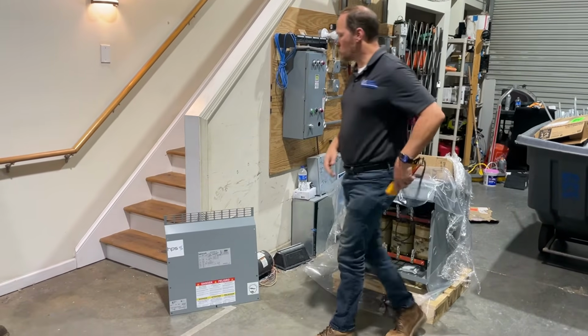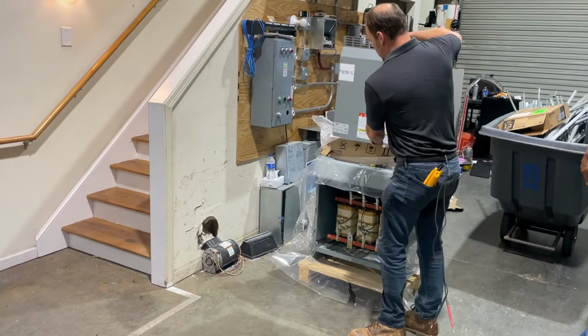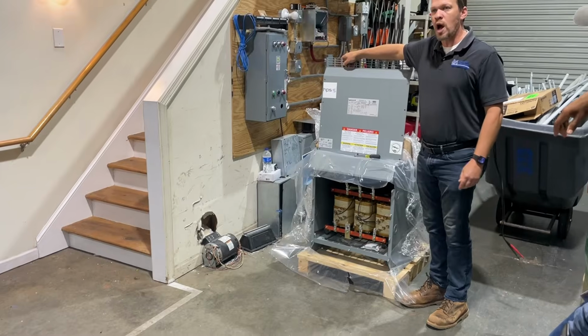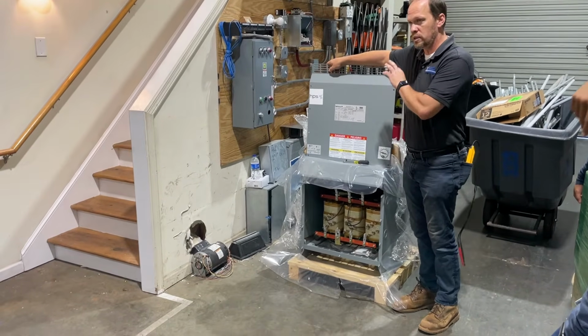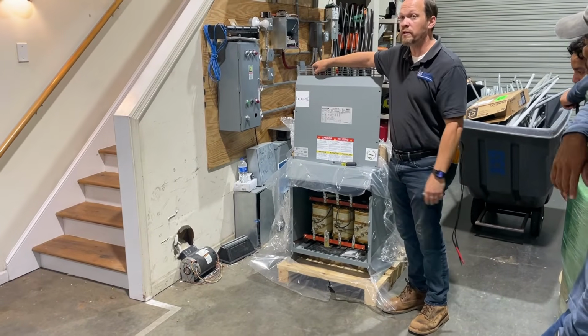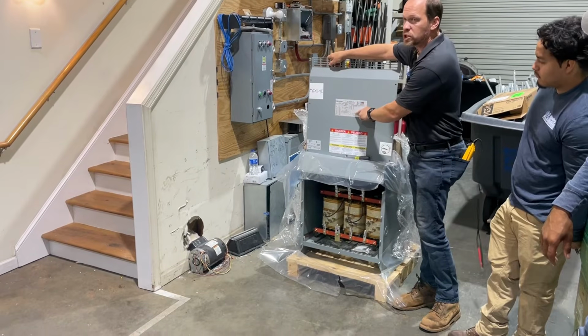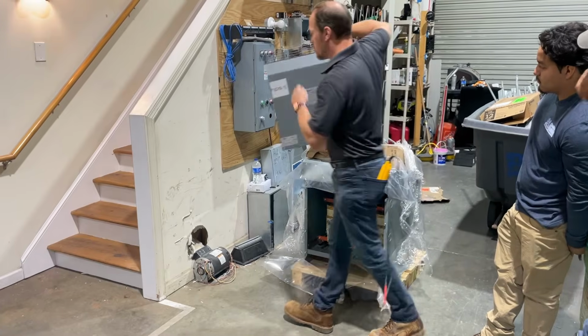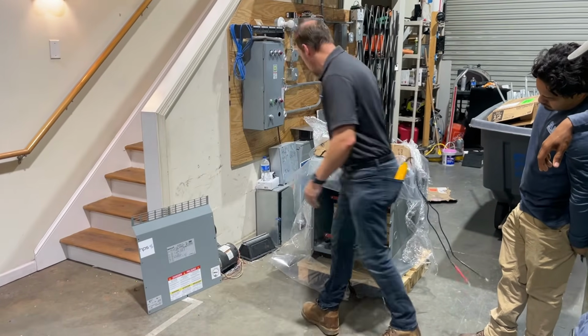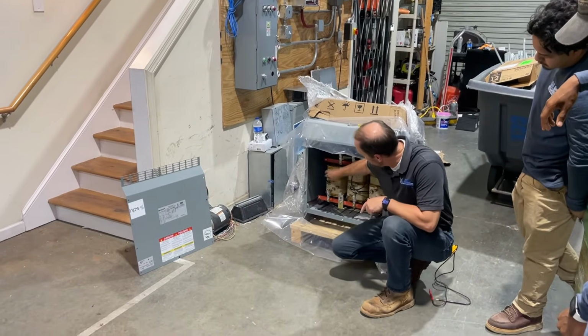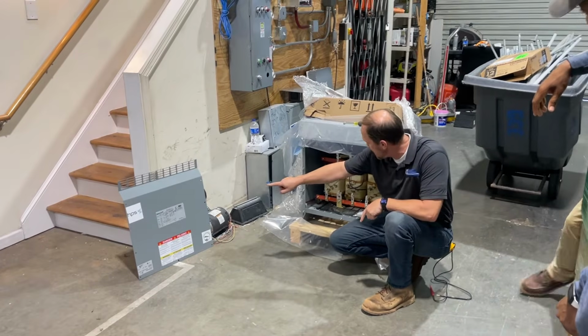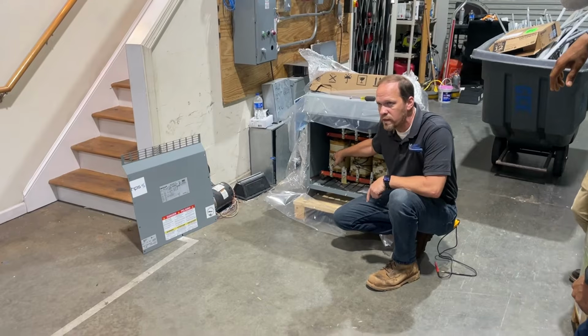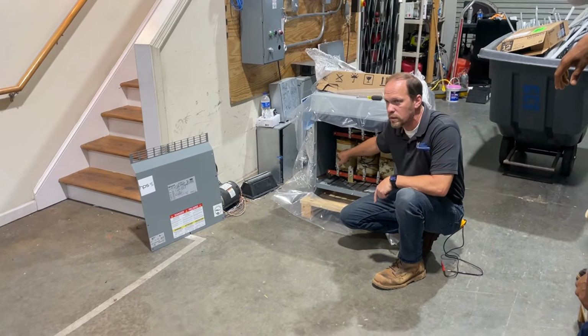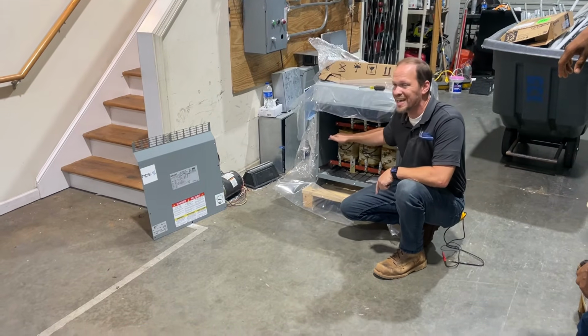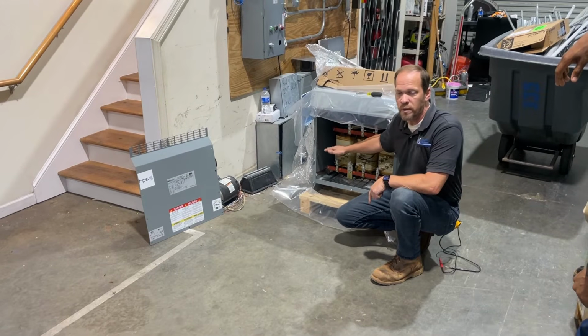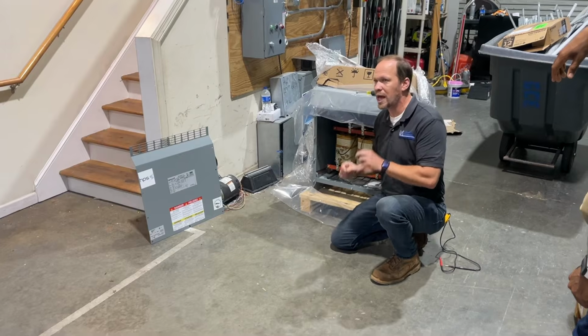Transformer taps are listed here as well. These are very important because if we need to account for a voltage drop coming in—say we have 240 nominal but actually have 230 or 228—you can use the transformer taps, which list the voltages you can have coming out. Instead of looking at how it's already hooked up, you use the numbers written on that sheet and change the tap on the front of this coil. All it takes is moving this wire to a different place, which changes the ratio just a little, so you come in with one voltage and come out with a slightly different voltage.